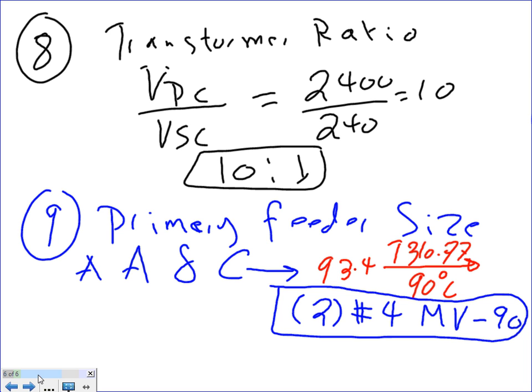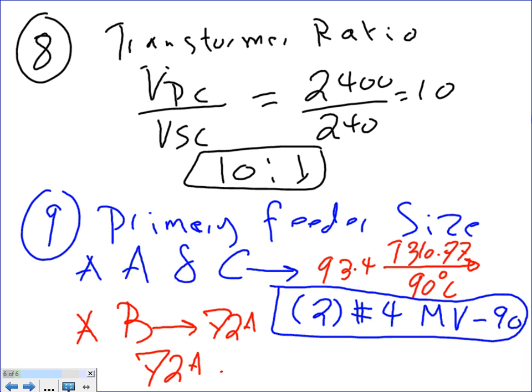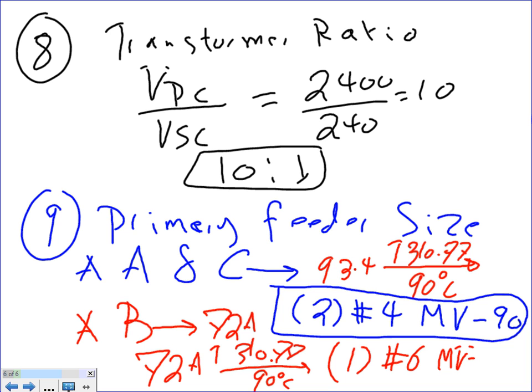The second one, guys, phase B. What was the current for phase B? 72 amps. Take the 72 amps to table 310.77 under the 90-degree column, and find how many conductors. One conductor. What size? Number 6. Is that what you came up with? Number 6, medium voltage dash 90.